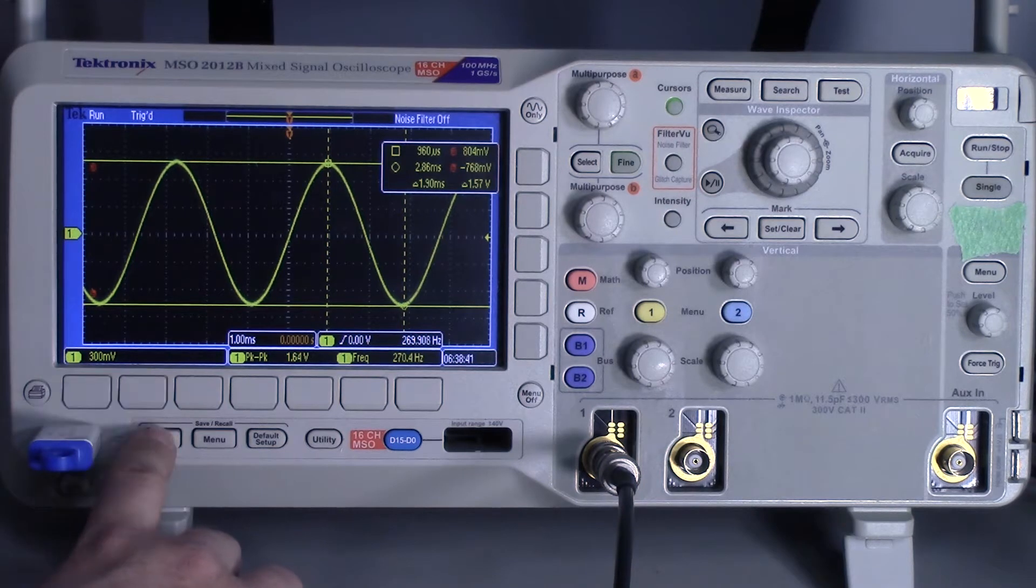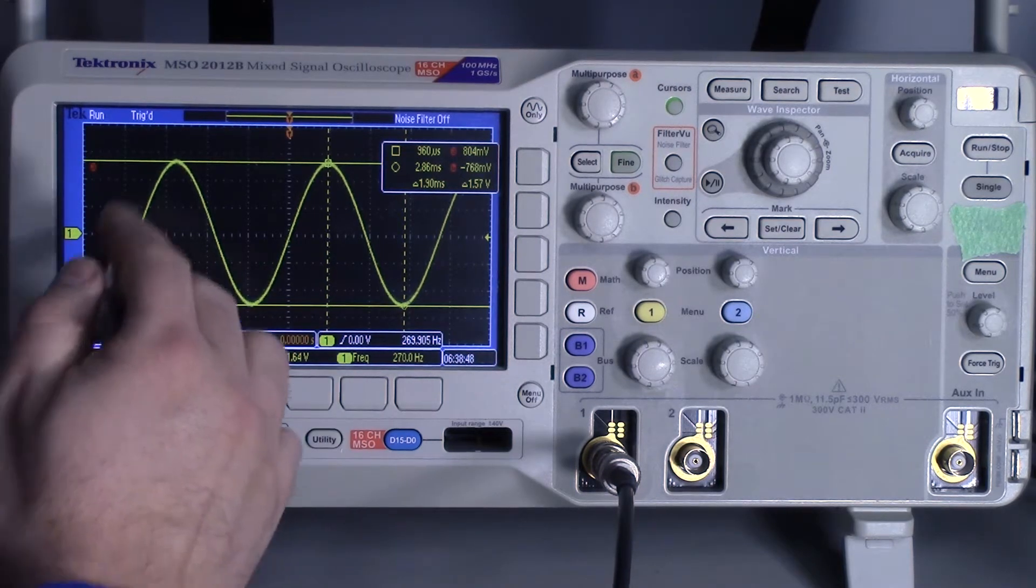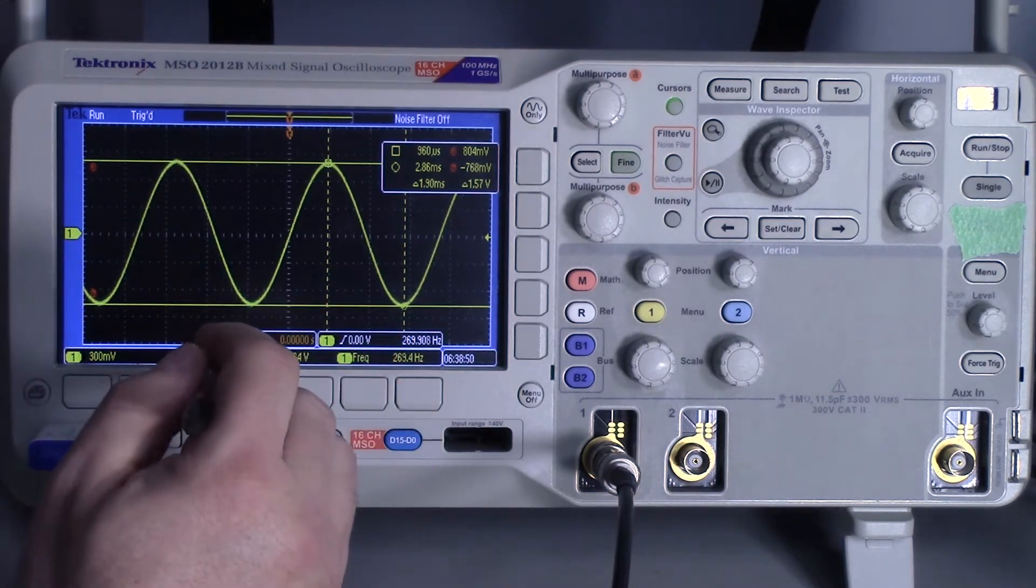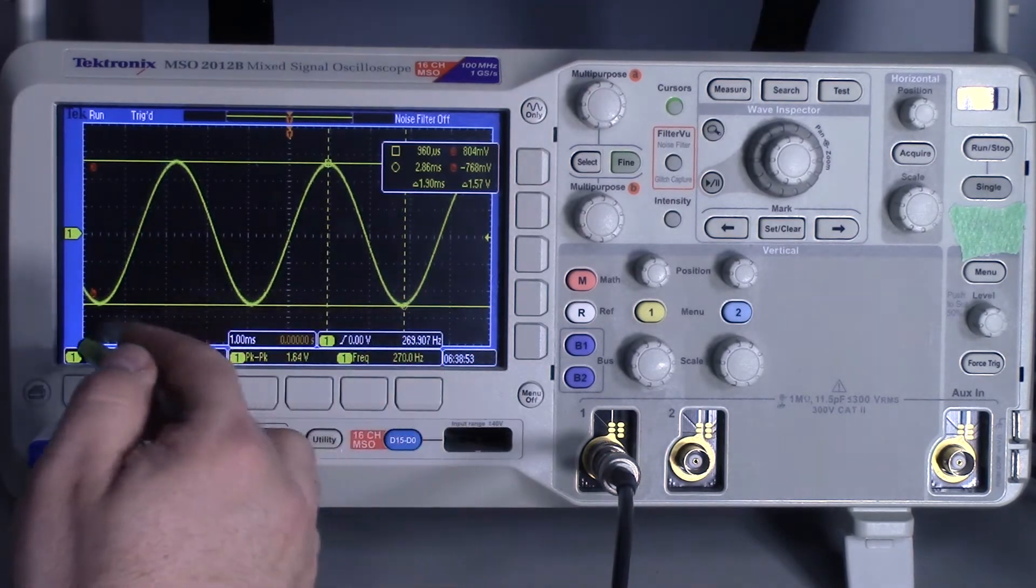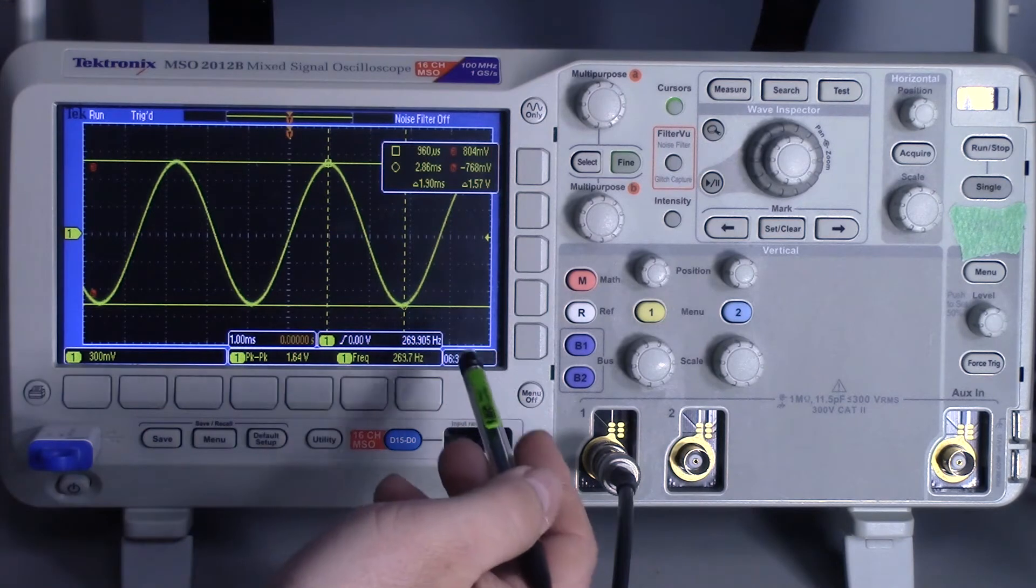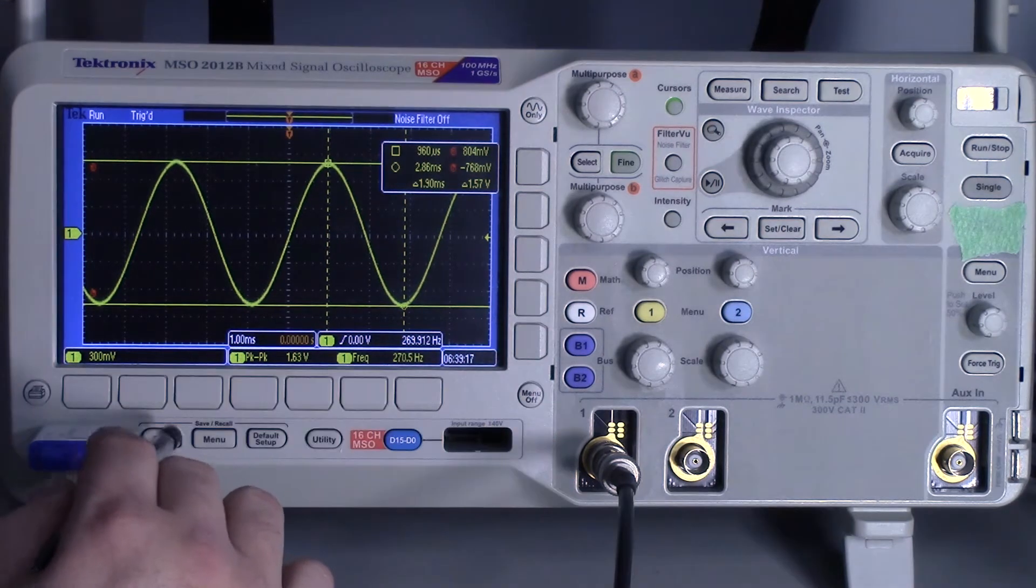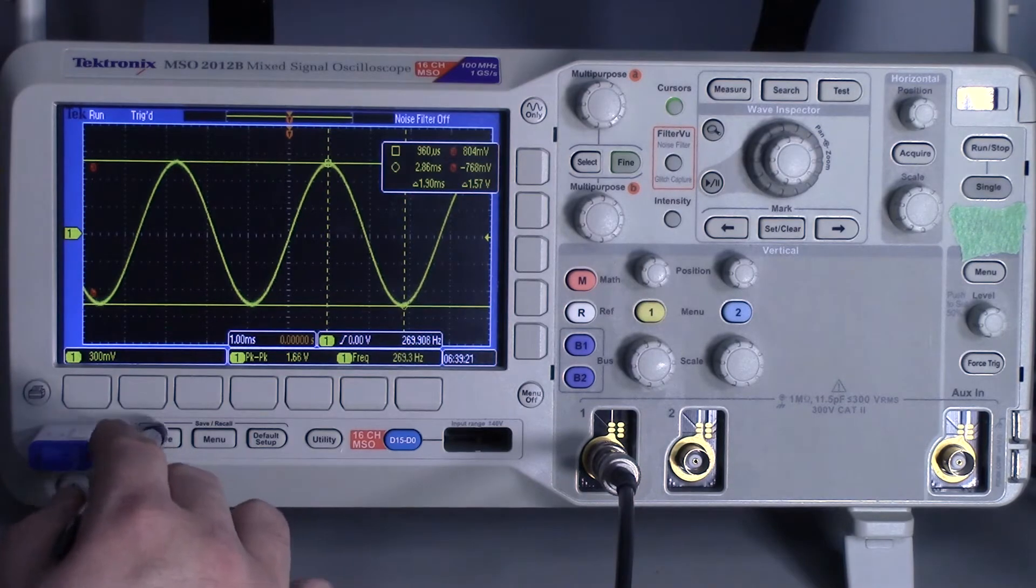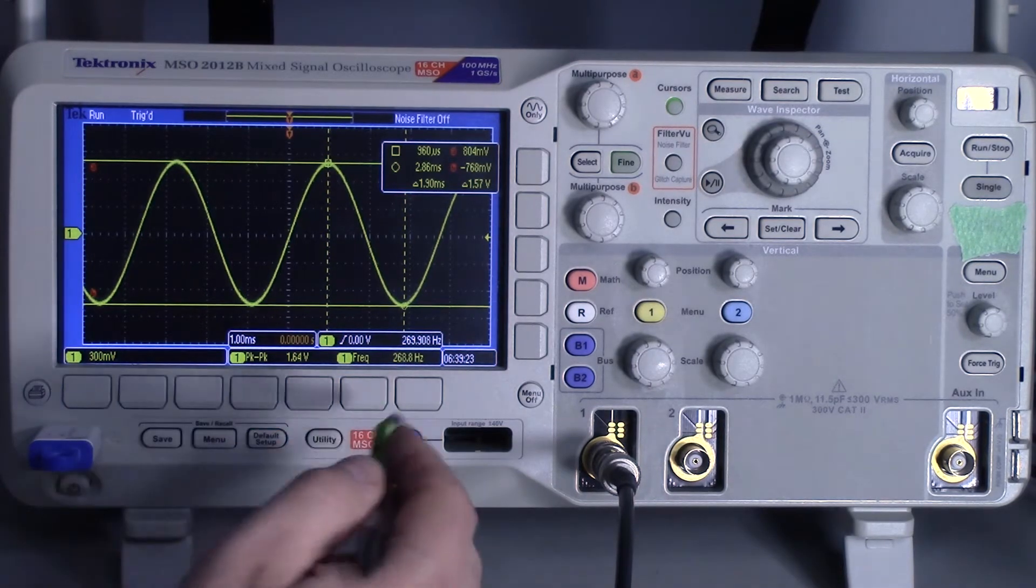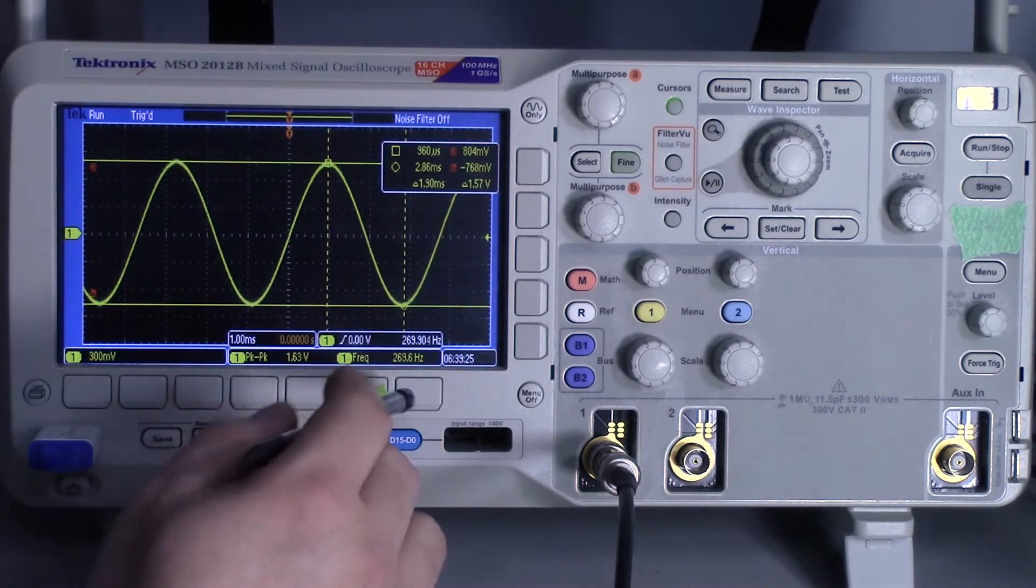If you expect it to save an image and it saves it as a waveform, you'll get a CSV file. You can reproduce the waveform, but then you're going to lose the scope image. Before you start taking measurements and just clicking the save button thinking that you're capturing an image, you want to make sure that's the case.